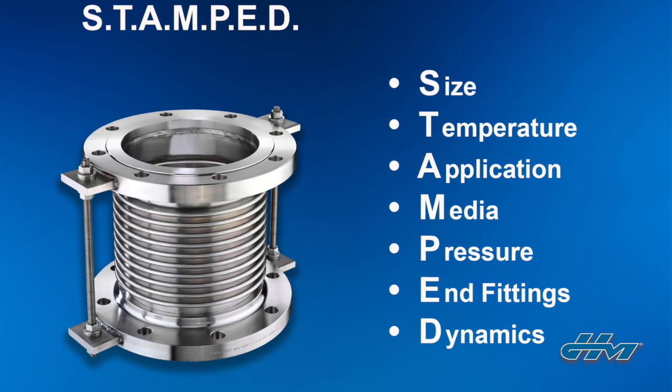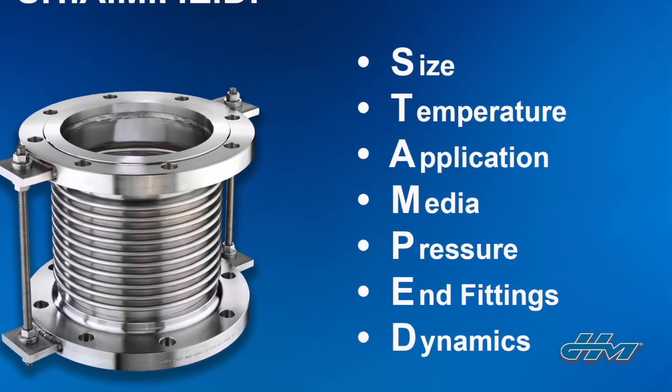We can still use the STAMPED acronym. However, because expansion joints are designed to handle axial movements — compression and extension — they are exerting stresses onto the piping system that hoses don't, as that's restrained by the braid on the hose. So with expansion joints, we have to ensure by getting additional information from the customer that they're installed in a properly anchored and guided piping system that's able to withstand those stresses exerted on it as that expansion joint is pressurized and moves around.